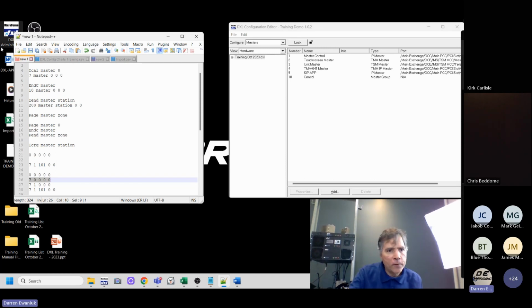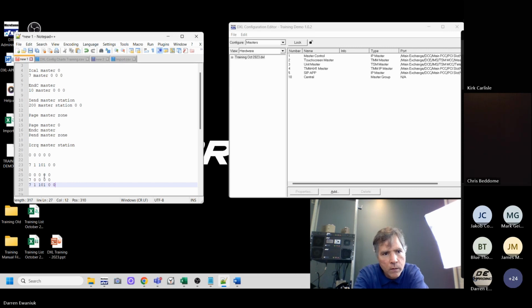So when this first register is written into, it's going to act on whatever it sees in the rest of the command. But the command is incomplete yet. You haven't filled in the rest of the registers, so this command wouldn't work properly because the command wasn't filled in when that first register was updated. Later on, the intent was to send 7, 1, 101, so it doesn't act on the command because it's all 0. Ultimately you'll write all the values in, but it hasn't connected to anything, it's still connected to nothing.